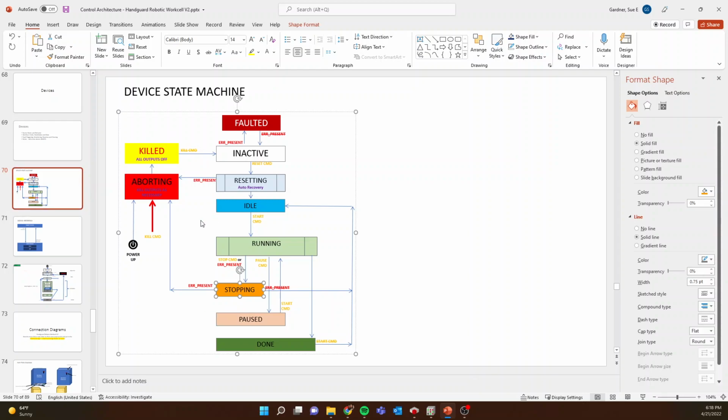that parent would take itself to the inactive and faulted state, and then the grandparent would be reacting as well. It would likely be issuing a stop command as kind of an echo, back to that parent device, and then once the parent device is done, that grandparent would take itself to a faulted state.